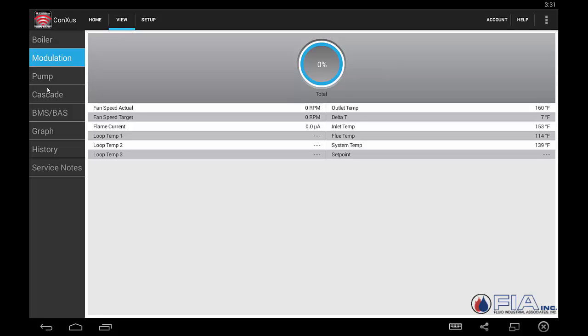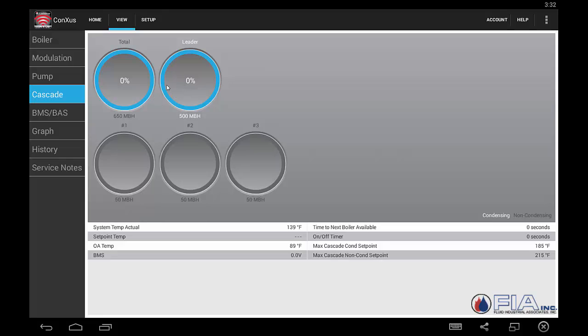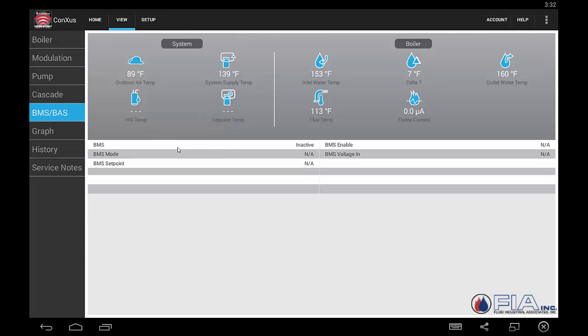The cascade screen gives us an idea of what's happening currently in the cascade. This is the leader of a three-boiler setup. Notice it says condensing and non-condensing — the Lochinvar smart control has the ability to do a mixed plant. For example, you could have a copper fin boiler connected with an FTXL boiler, and front-end load it in the shoulder months with your Lochinvar FTXL. Moving to the building management screen, it shows that our building management is currently inactive — we're not using it at this site.